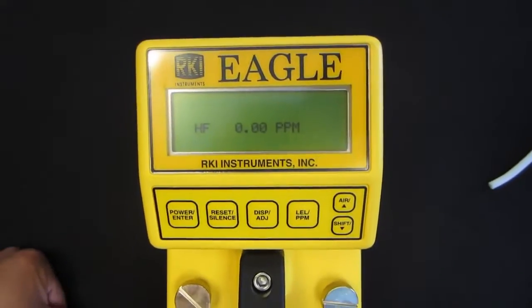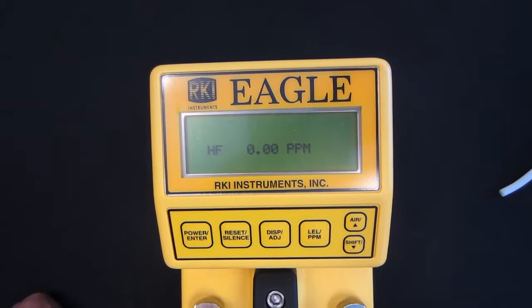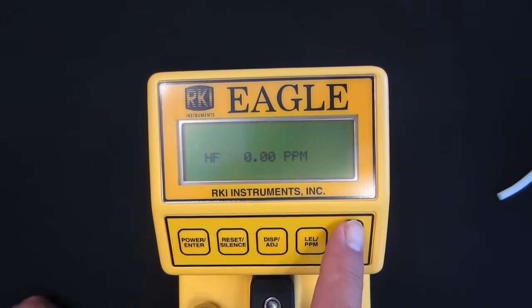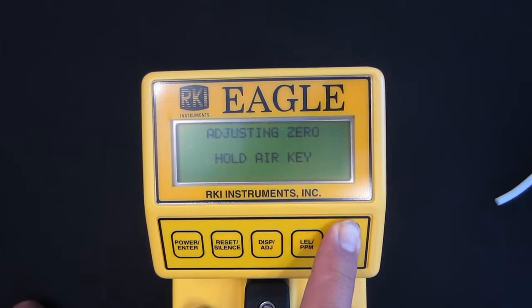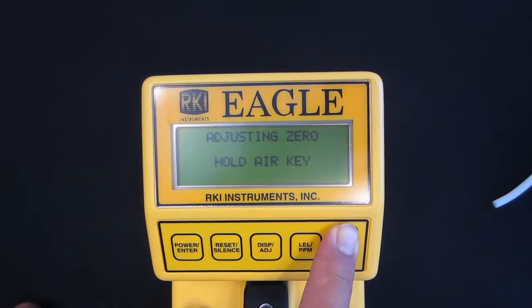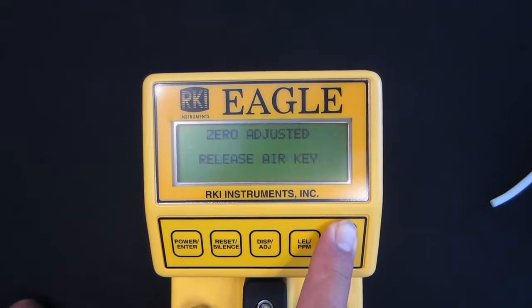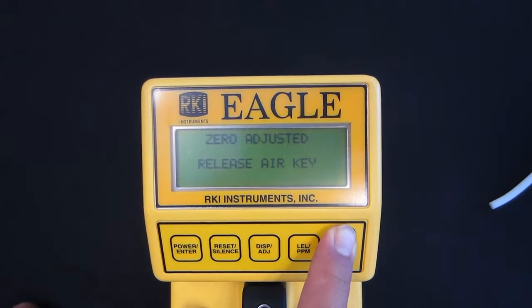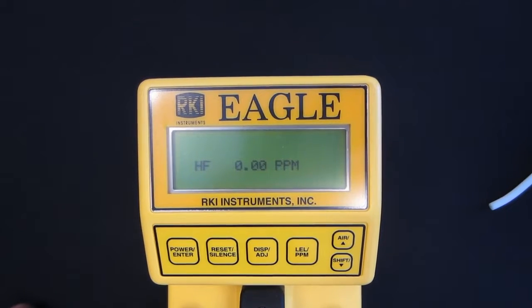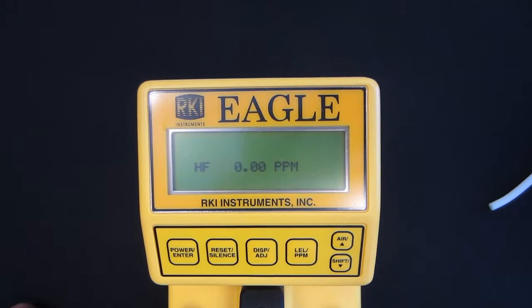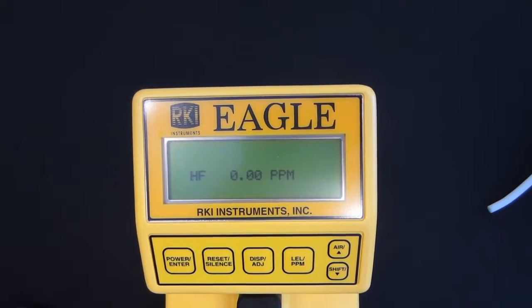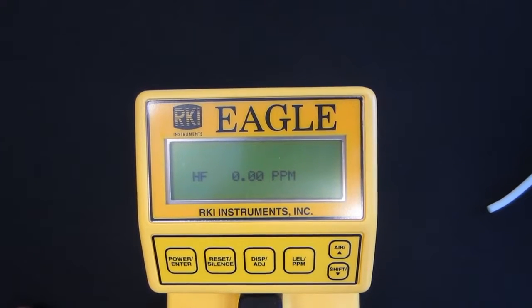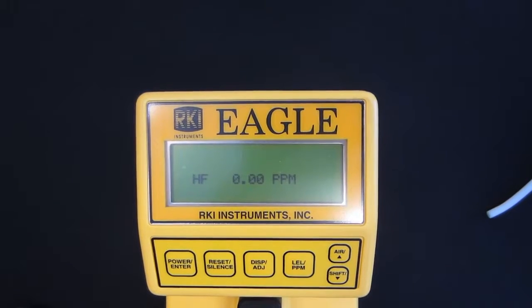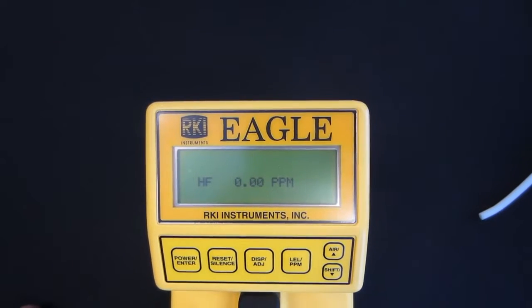Okay, first of all, we're going to air adjust the unit. We're going to press and hold down the air key. Even though it says 0 right now, we want to do this before we do an actual span with gas. The unit is telling me to release the air key, and it has properly zeroed itself to a clean atmosphere. And of course, you want to make sure you're in a clean atmosphere whenever you air adjust or zero out a sensor, as we call it.